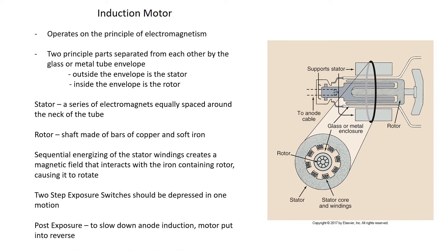Post-exposure, the anode slows its spin because the induction motor is put into reverse, which allows the anode disc to stop spinning.